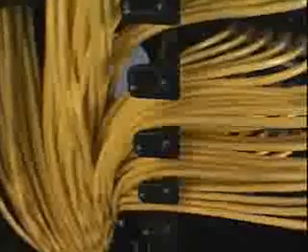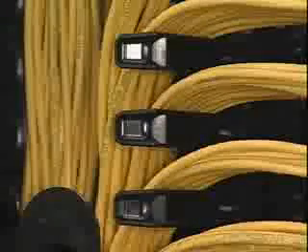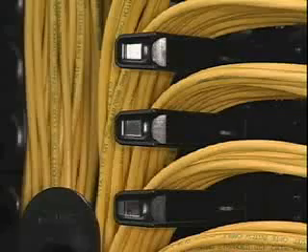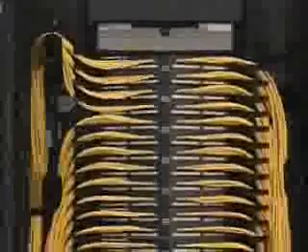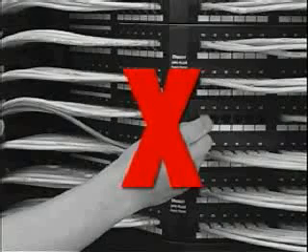Properly routed cables should lay over the finger without crossing over one another. The angled panel minimizes cable strain by promoting proper bend radius of the cable as it goes away from the patch panel. This requires that the patch cables on the left side of the panel be routed to the left and the right side to the right. Do not route cables on the left side of the panel to the right and vice versa.